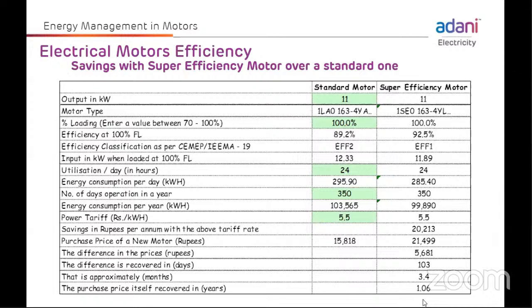But they are not thinking about the long term. That's why I am giving this example: this cost is higher, 21,499, versus 15,818. So the cost is a bit higher, but the payback period is approximately 3.4 months. Within 3 months this extra cost is recovered, and within 1 year the total cost of the motor will be recovered, and we get higher efficiency and energy savings.